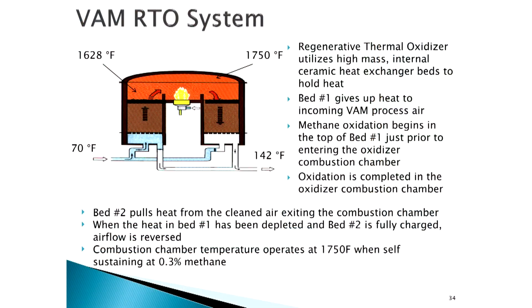It's a proven technology. It's deployed in Australia. It's deployed in China pretty extensively. And the first one in the United States is at the Verdeo mine in West Virginia. So the ventilation air methane systems are a very simple two-tower RTO, basically. The difference is that we have to be very careful about the concentration of methane we send it, because the air that we bypass and release from the combustion chamber, you see it's about 1,750 degrees here, but if the methane concentration is too high and that walks up to 1,950 degrees, you've got issues with the metallurgy of the dampers that we're dealing with and so forth. So there's some technique to it, obviously.